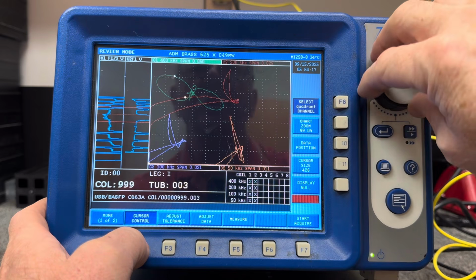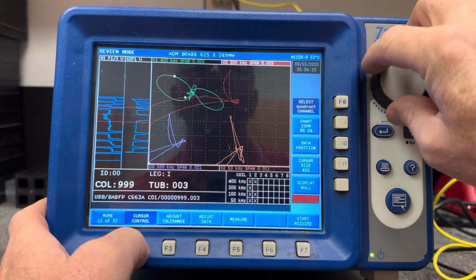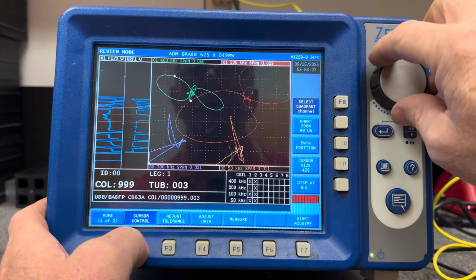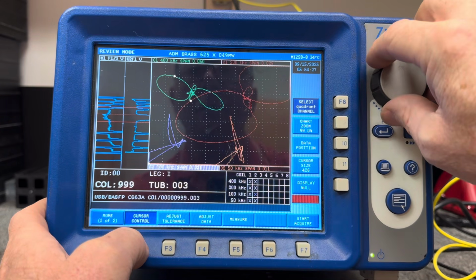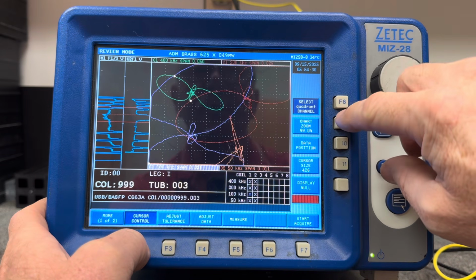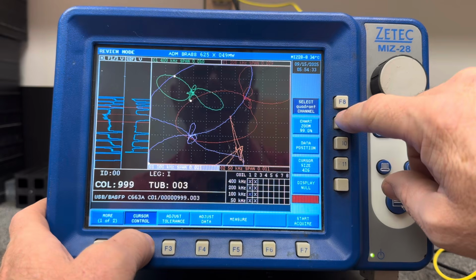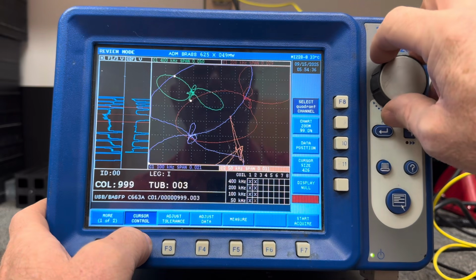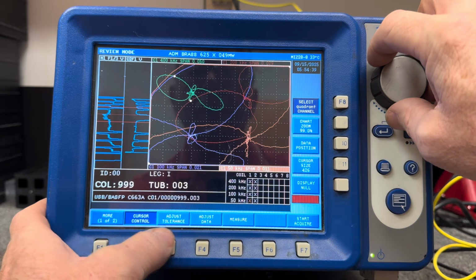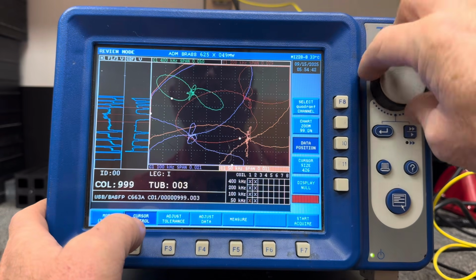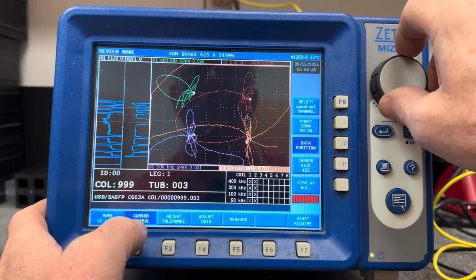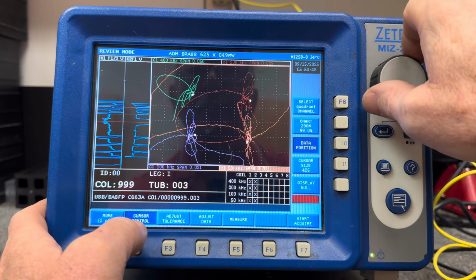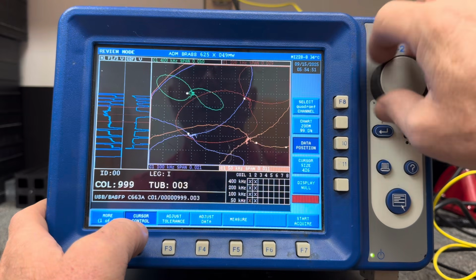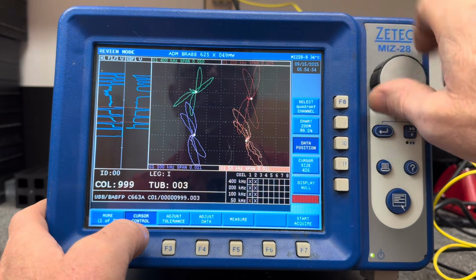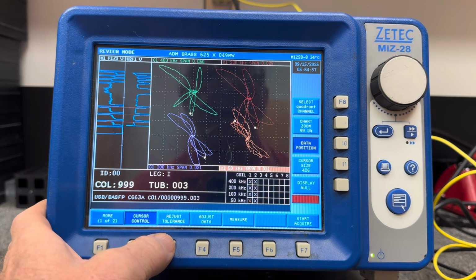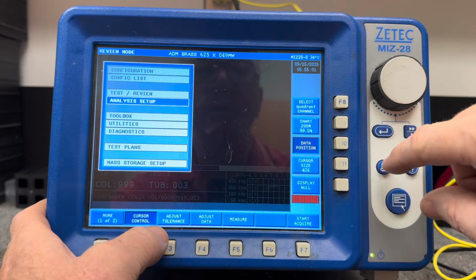there's a support plate on 400 kilohertz. There's 200 kilohertz differential. 100. Obviously it's bigger because it's lower frequency. And finally, there you go. There's your support plate. And these are your wear scars here. You'd perform a 2-channel absolute mix for sizing wear scars, probably, although you can do it with differential. And there's your 160/20.